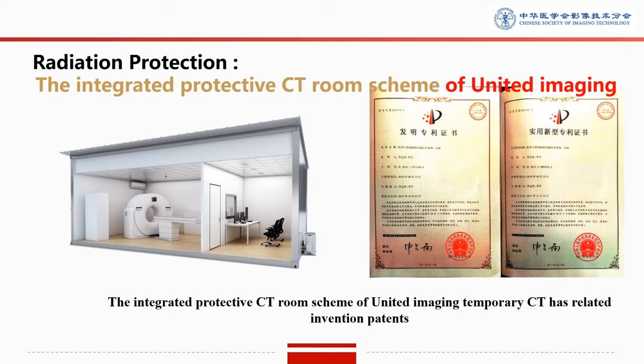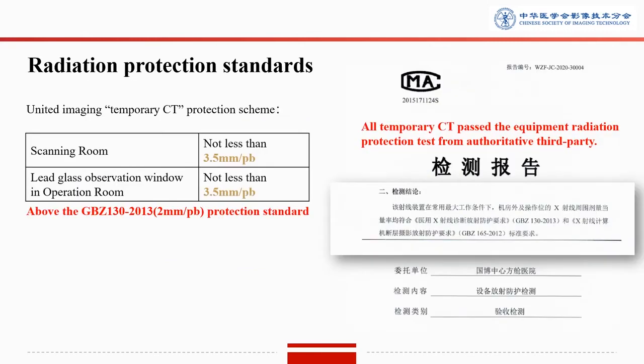CT is imaged by X-ray, so radiation protection is very important. The temporary CT from United Imaging is designed with an integrated protective CT room scheme, and they have also proposed a patent for this design. This protective scheme has passed testing from certified third parties, and all radiation protection standards are above the state FDA standard.